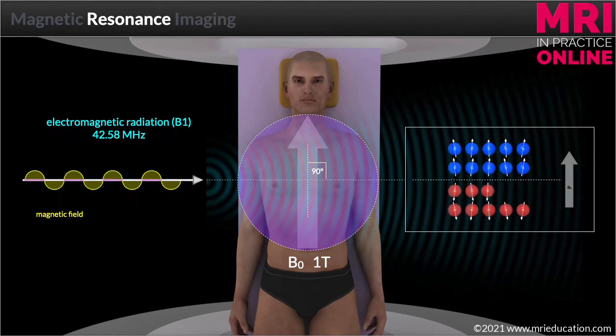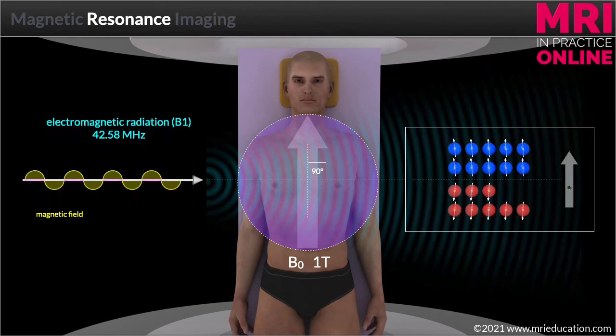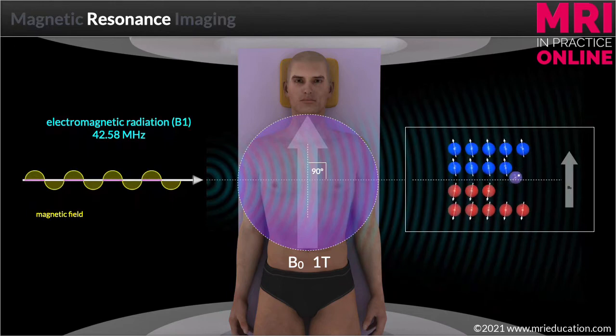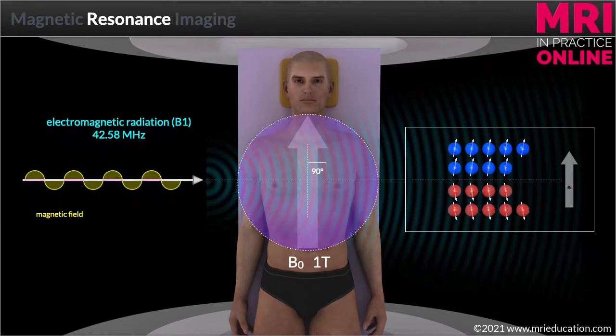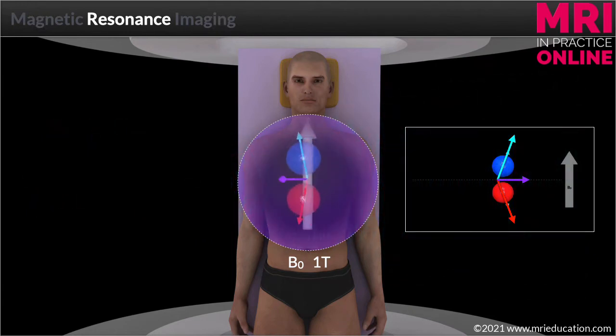When we apply this RF pulse, two things happen. The spins start to precess in sync — we say that they are in phase. And because resonance involves a transfer of energy into the system, some of the low energy spins will gain enough energy to oppose the main magnetic field. The scanner can calculate the exact amount of energy required to balance the two spin populations. You can see on the model that we now have as many blues as reds. By applying the RF pulse we have flipped the net magnetic vector into the transverse plane, 90 degrees to B0, shown here by the purple arrow.